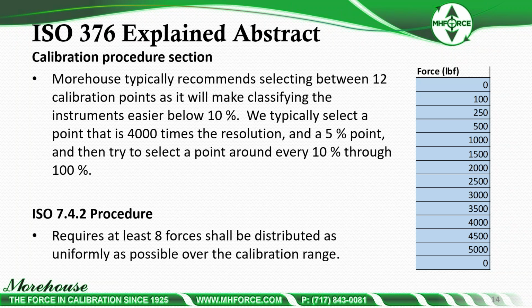We do this because if the instrument does not meet class 00 at 2%, it's not going to meet it at 5% either, and if we don't take that 5% point till probably 10%, then from that 2% to 10% you cannot use it in that class 00 range. So we take a 5% point, and in most cases, the instrument will meet at the 5% point if it's a good load cell or good force indicating instrument.